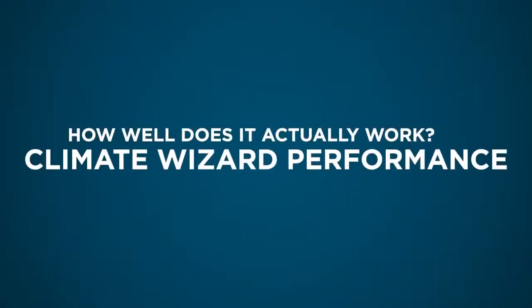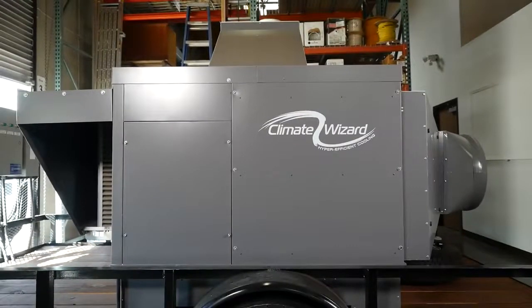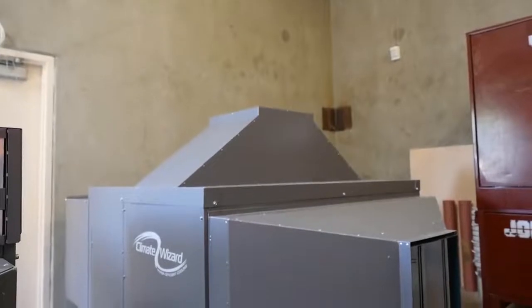Everybody has doubts first. What we had to do is monitor it, put the control system in so they could see instantly on their computers what the outside ambient is and what the supply air temperature was. Seeing is believing. We actually brought the units into our office and did extensive testing on them. And so we saw what it could do with ambience in the range of 115 degrees.